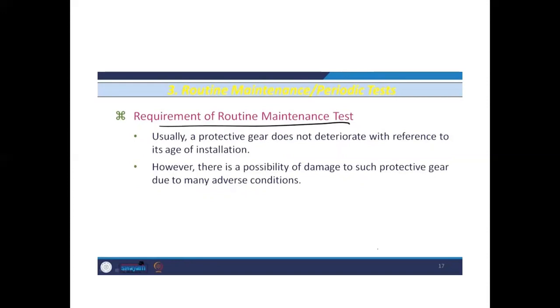Requirement of the routine maintenance test. Usually, a protective gear does not deteriorate with reference to its age of installation. However, there is a possibility of damage to such protective gear due to many adverse conditions. For a relay, the number of operations is shown on its counter, and we can see on this counter how many times this relay or the circuit breaker has operated. There may be a case that in many adverse conditions it is damaged. So this should be periodically checked, whether it is working properly or not.